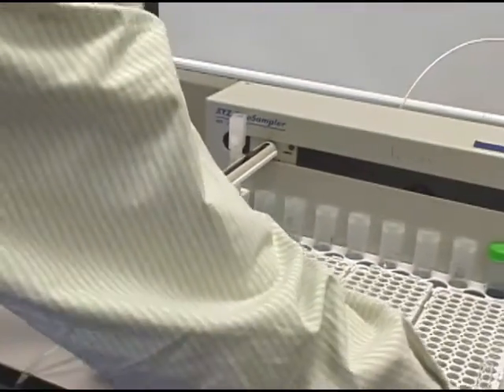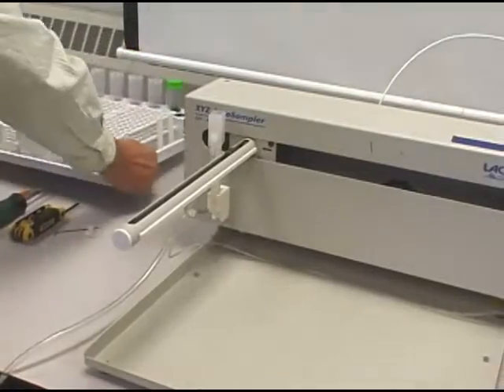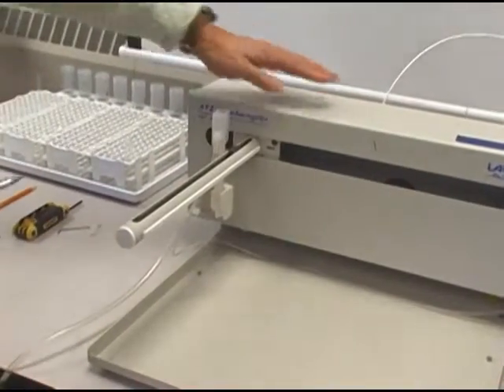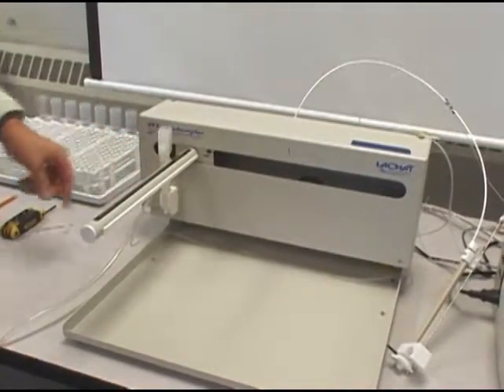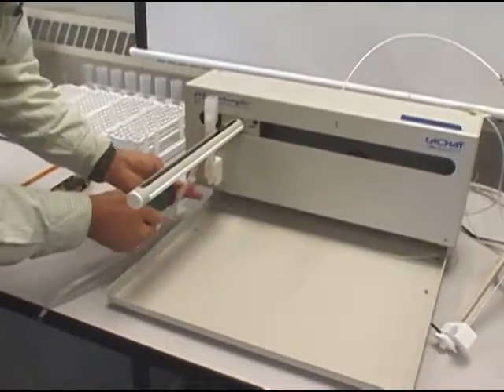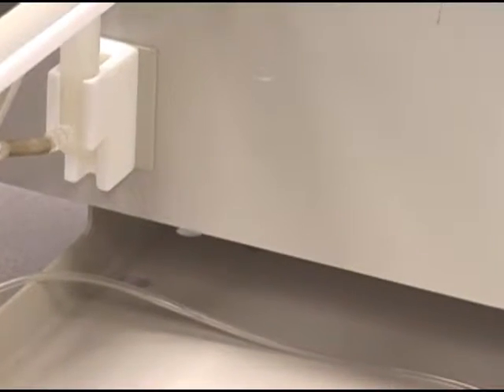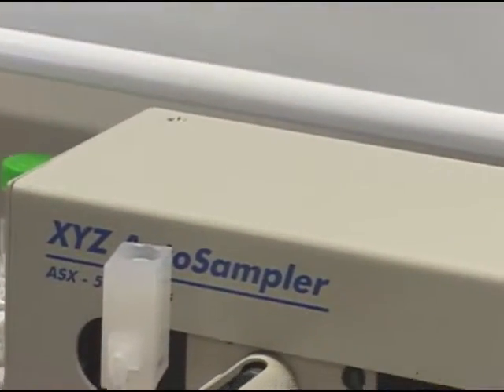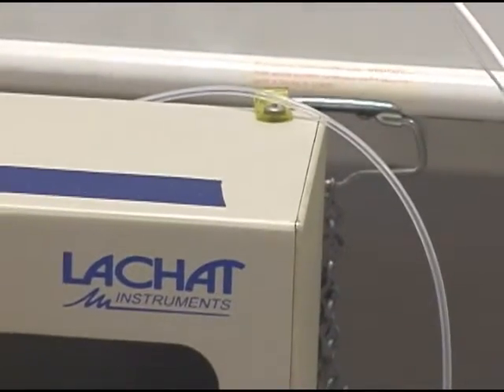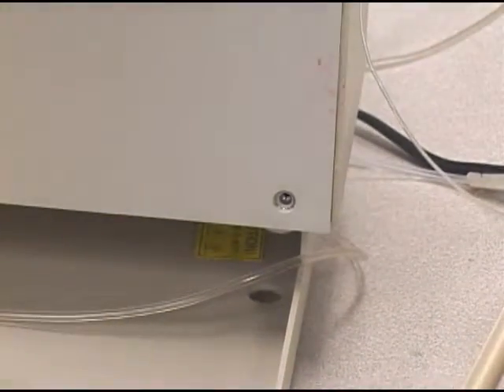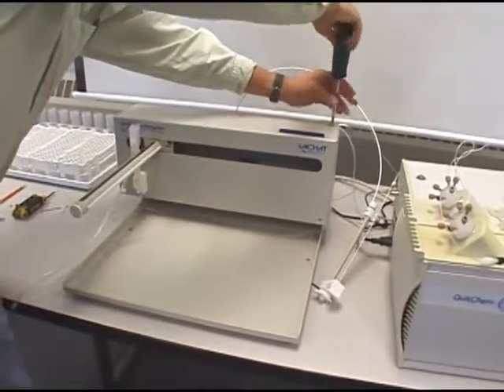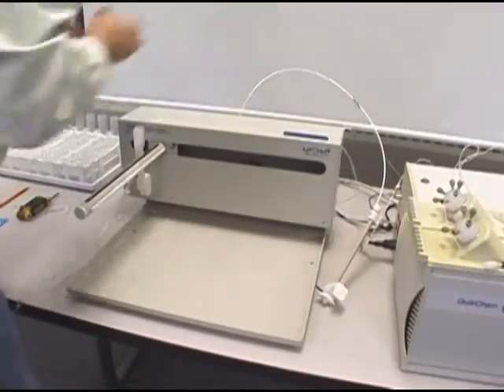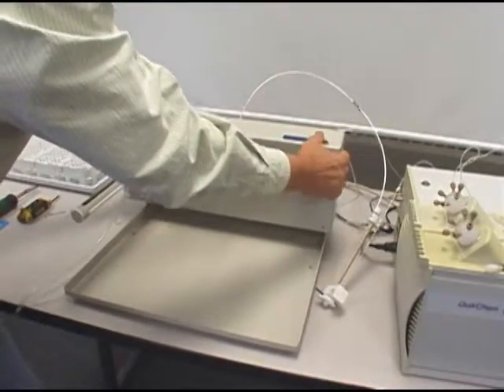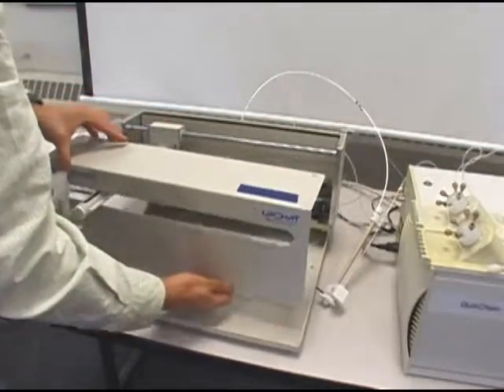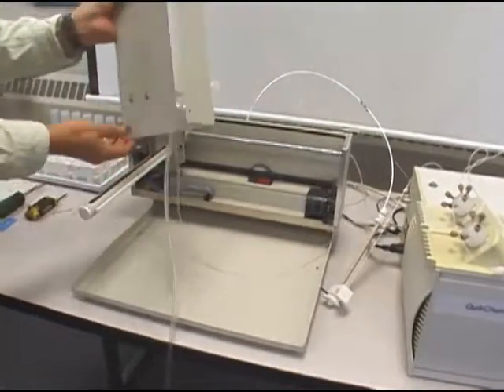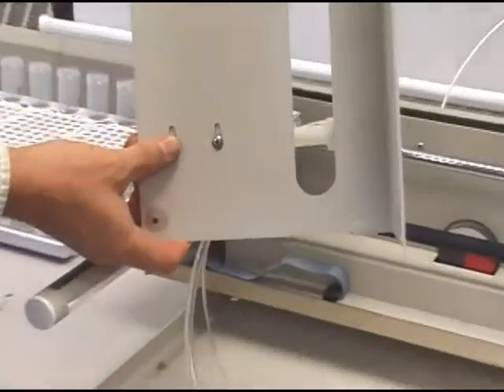We now need to remove the tray. And we need to remove this cover so that we can access the screws on the back of the wash bath. There are 4 screws, one on each corner of the main carriage on the auto sampler. We'll remove all 4. And now we can take this front cover off. And on the back of the front cover, you see the 2 screws that hold on the wash bath.